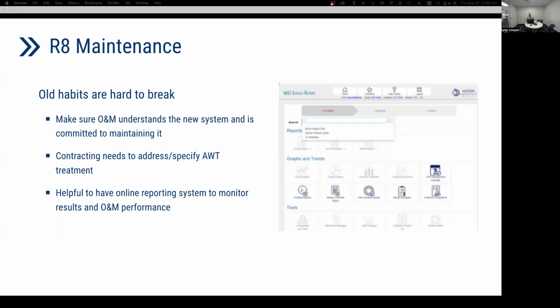So in terms of maintenance, because we were early adopters with this, we did run into some maintenance difficulties. Within this, training with the O&Ms and incorporating that into the contracts were two of the main takeaways. Making sure the O&Ms know how to operate and maintain those alternative water treatment systems is critical, and actually incorporating them into the contract requirements as a maintainable asset versus prescriptive water treatment parameters that you need to maintain with those cooling towers.